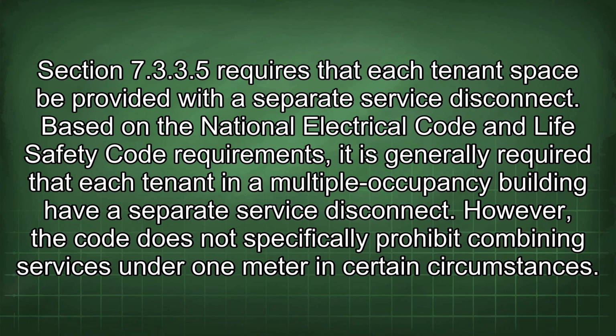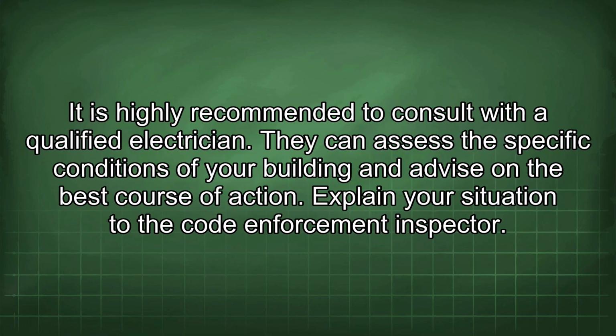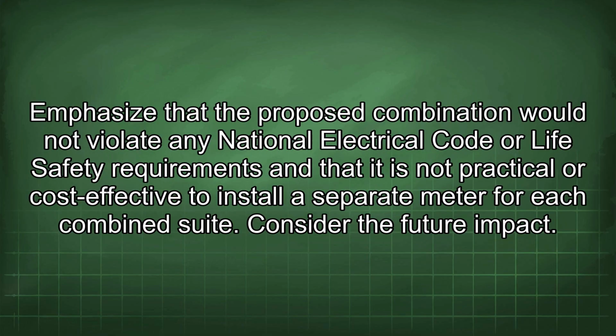However, the code does not specifically prohibit combining services under 1 meter in certain circumstances. It is highly recommended to consult with a qualified electrician. They can assess the specific conditions of your building and advise on the best course of action. Explain your situation to the code enforcement inspector. Emphasize that the proposed combination would not violate any National Electrical Code or Life Safety requirement and that it is not practical or cost-effective to install a separate meter for each combined suite.